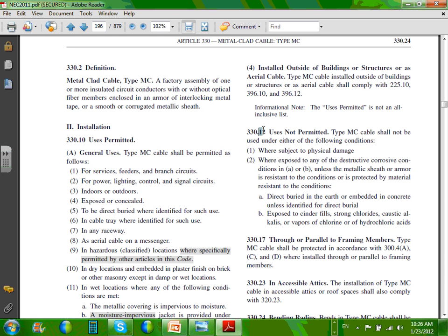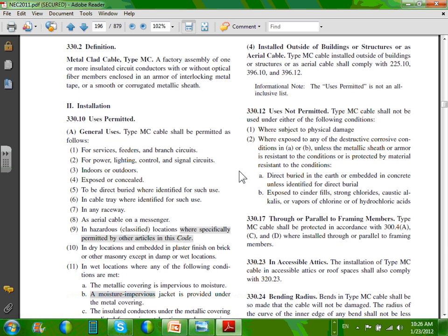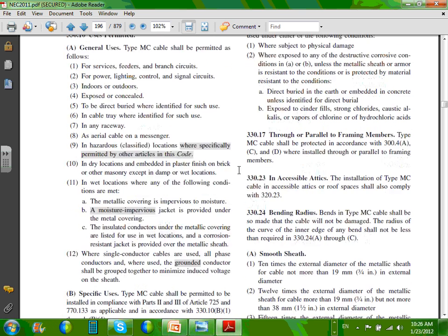I want to go all the way. Why can't you use it? Not permitted where subject to severe physical damage. If Chad is going to drive his Suzuki into it, you can't use this cable. So this is very, very important, guys, to know that dot 12 is used as not permitted, dot 10 is used as permitted. And we talked about, I don't want to get into all the itty bitty of it, guys. I told you where we use MC cable in dry location, unless you're going to use it in wet location, it has to be rated for that.